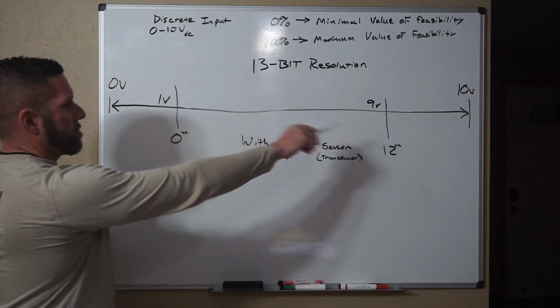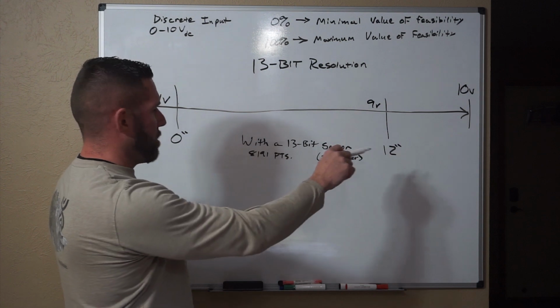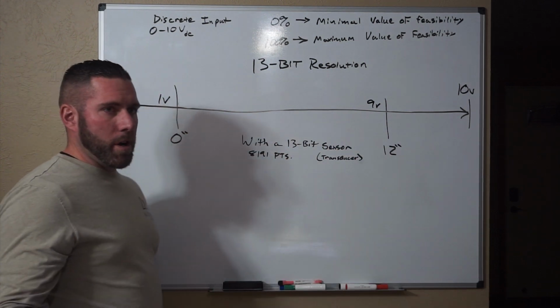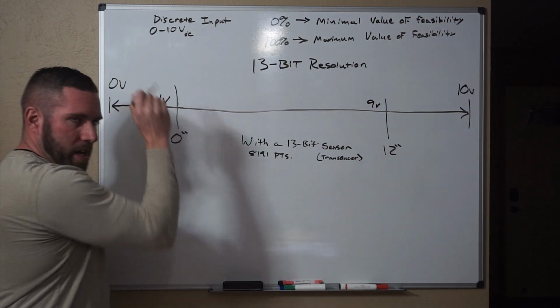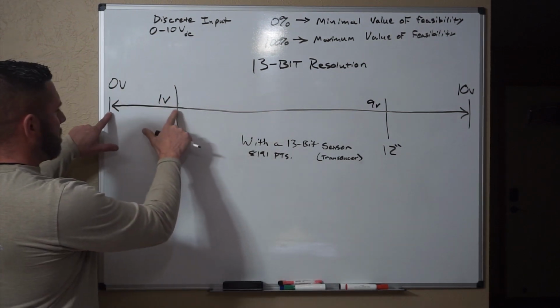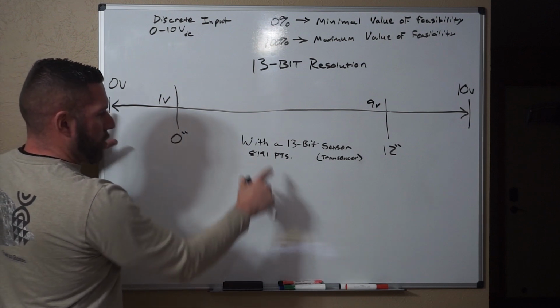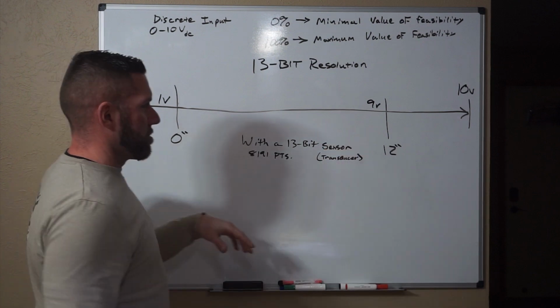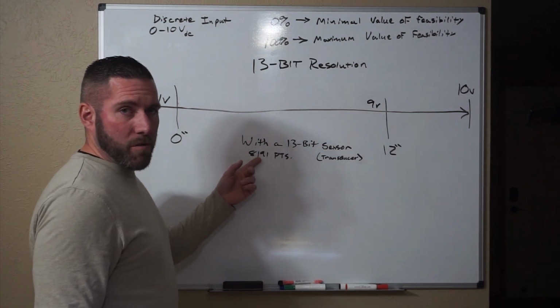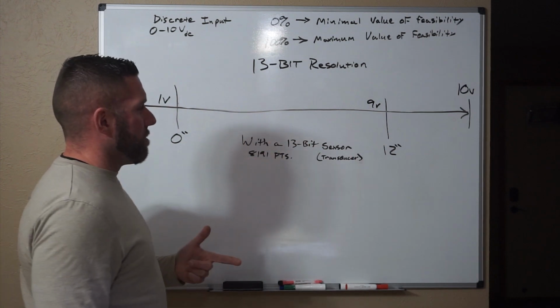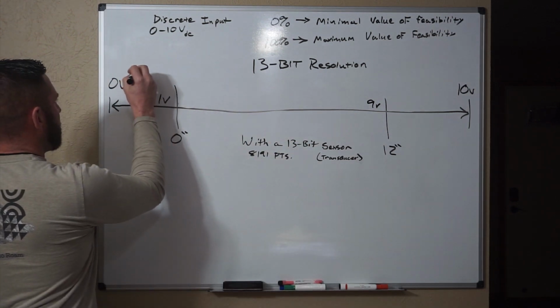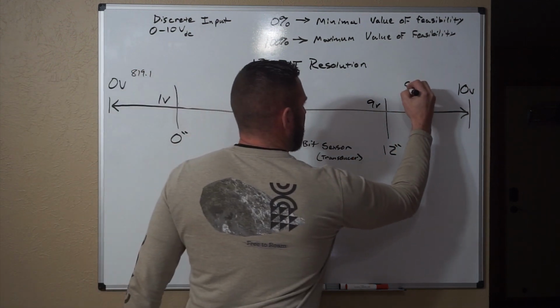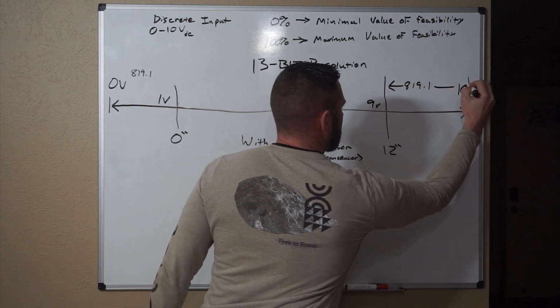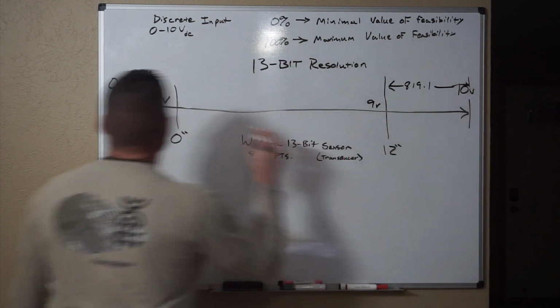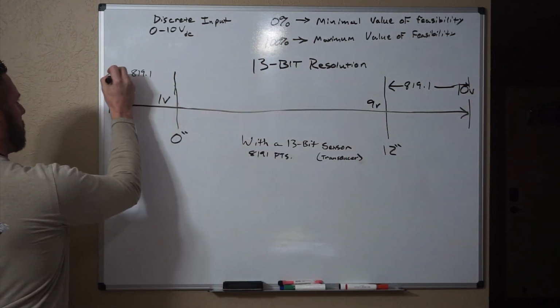So when we look at this right here, our 0 to 10 range is going to be 819.1 little measurements before it hits 1 volt. So between here and here, we can fluctuate 819.1. The way I got that was, it's over 10 volts, you would divide this number by the number of volts you're trying to read. We need to see 12 in this range. So over here, we have 819.1 above, and over here, we have 819 below. So now we have our buffer.